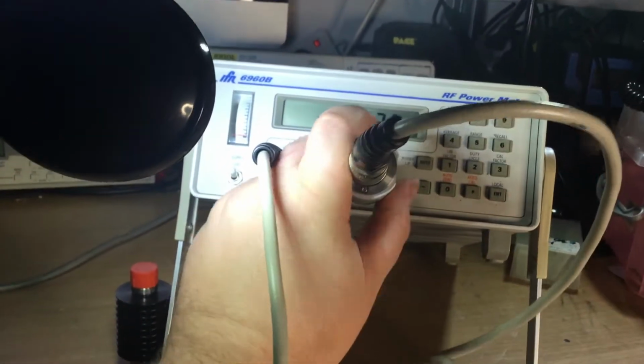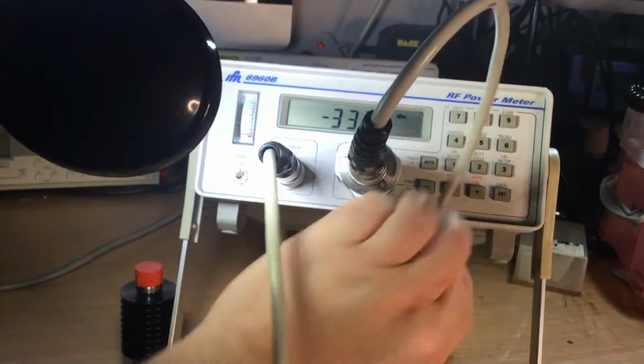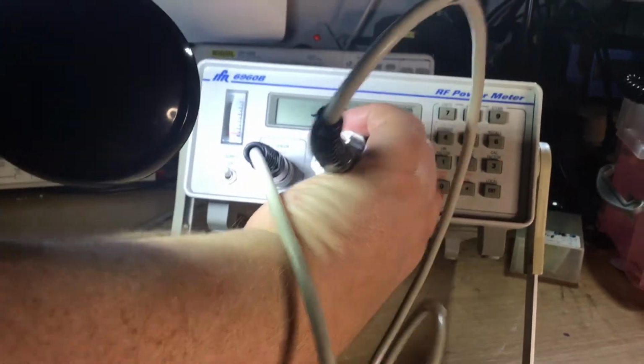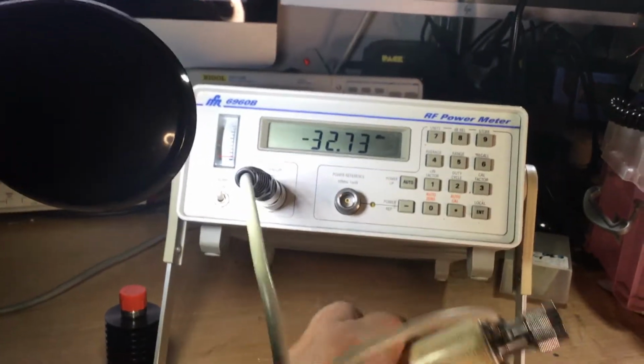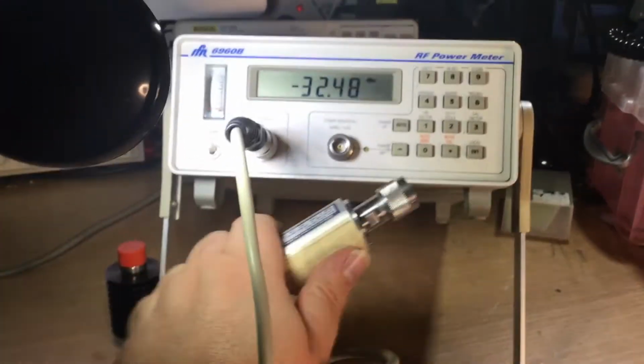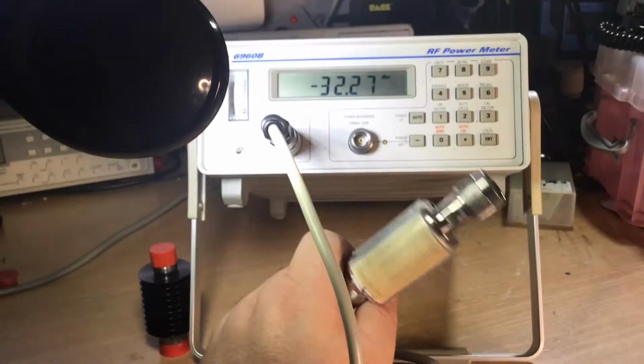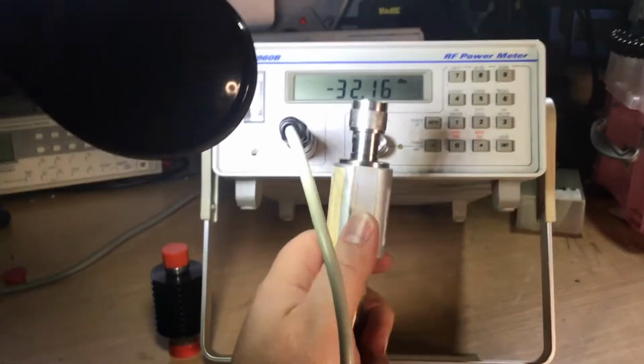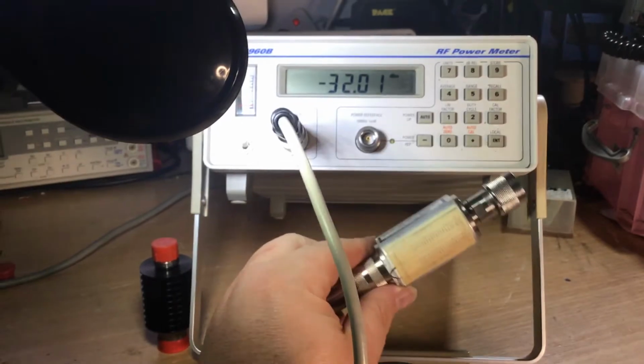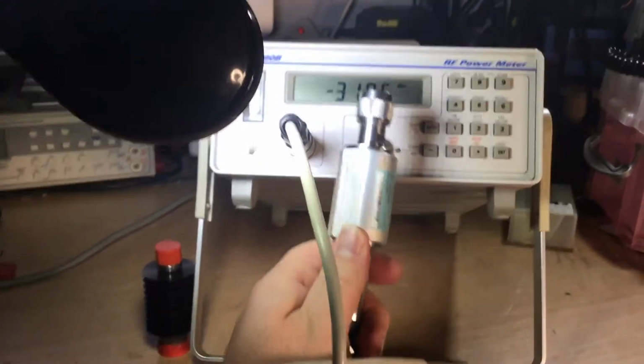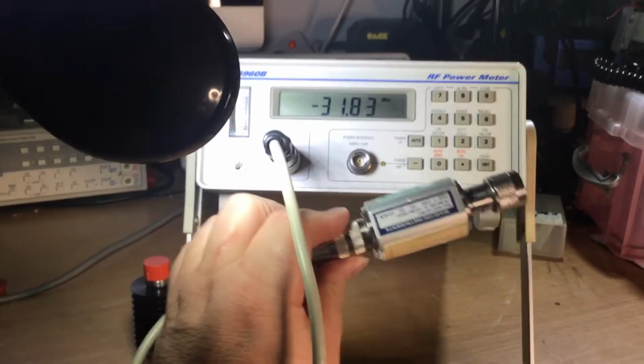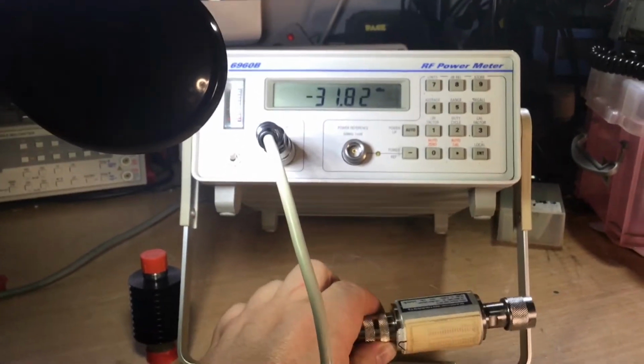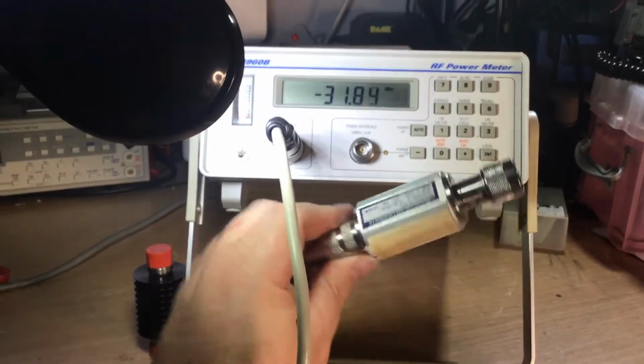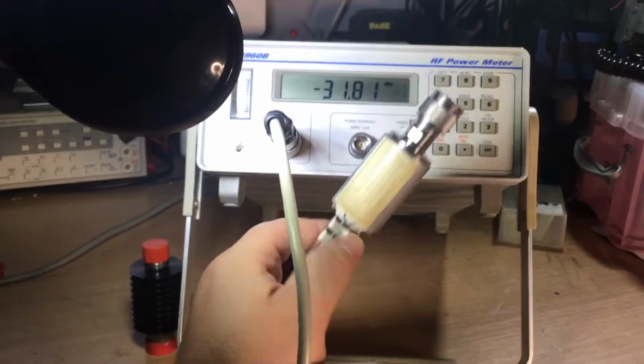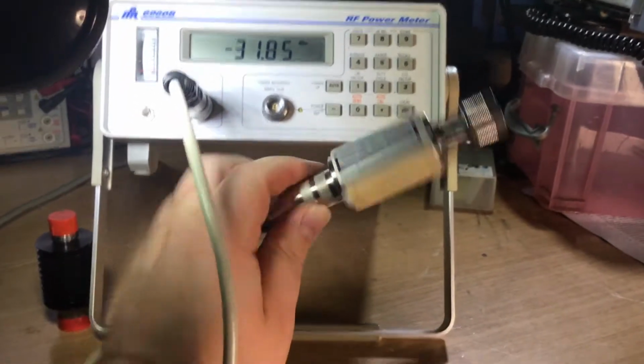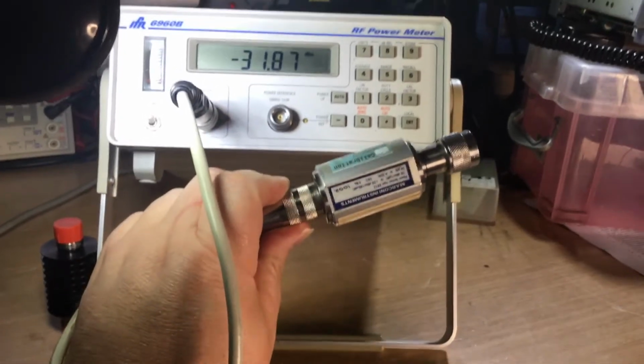You know, when you're looking at amplifiers, small signal amplifiers that are mast fed up the centre of a coax, microwave radio links for example, that again are fed with a 48V DC bias, it can burn them out quite easily, because it's not designed to take a DC bias unless otherwise noted on the labelling. So these sensors themselves are often more expensive than the instrument on its own, because all the tech, if you like, the measurement capabilities, is in the sensor, not in the instrument.